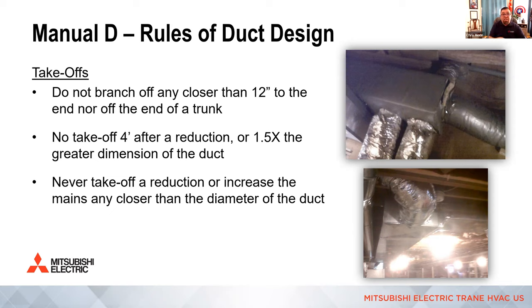And then of course you never take off a reduction or increase the mains any closer than that same duct diameter, right? Because it'll give you the same effect. It'll depressurize the rest of the trunk and all the air will go to that one spot. So even though it's convenient and you have a nice easy taper on that trunk, oh man, how easy would it be to avoid using 90s or a 45 and just come off the side there? It's going to be a problem. You're going to depressurize the rest of the house.